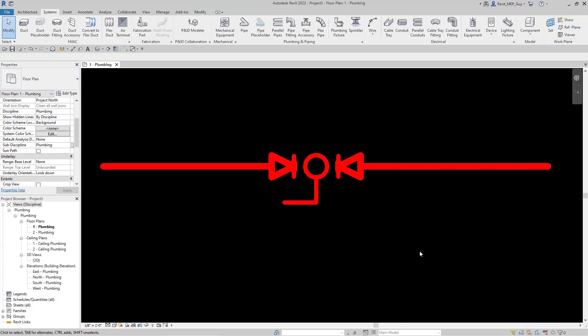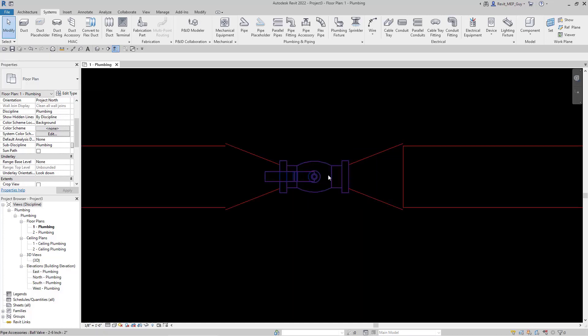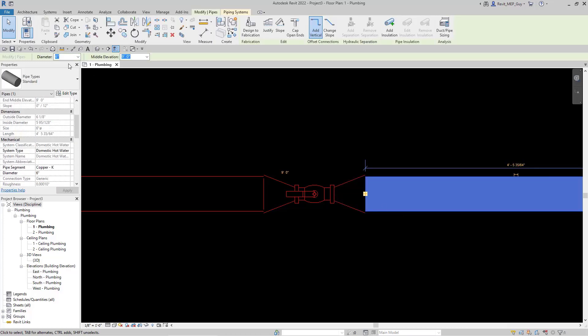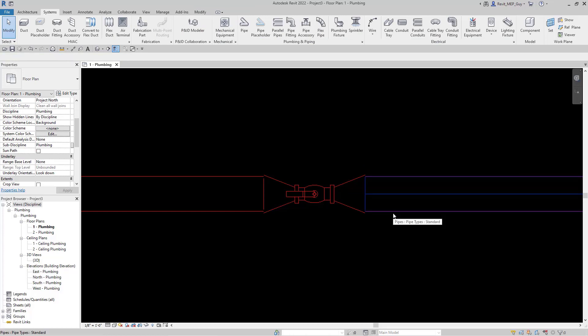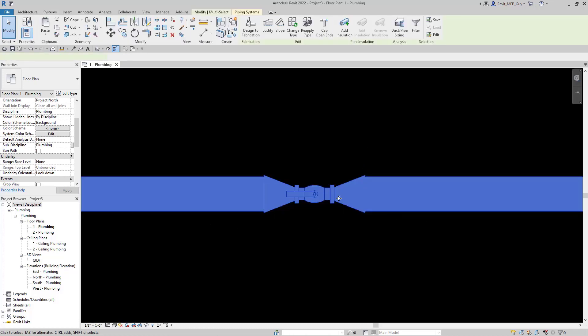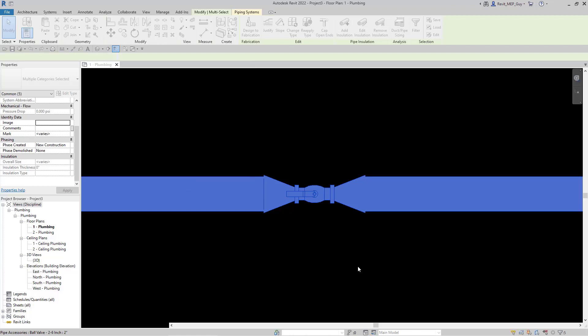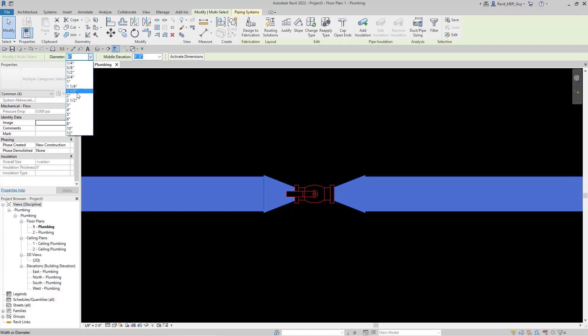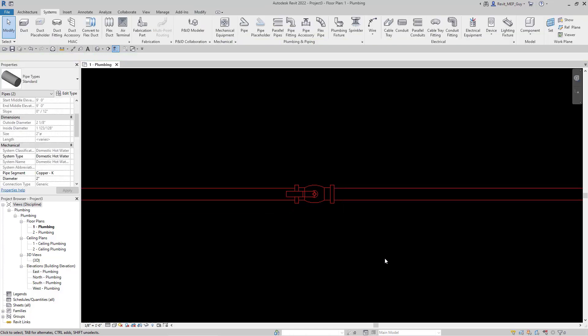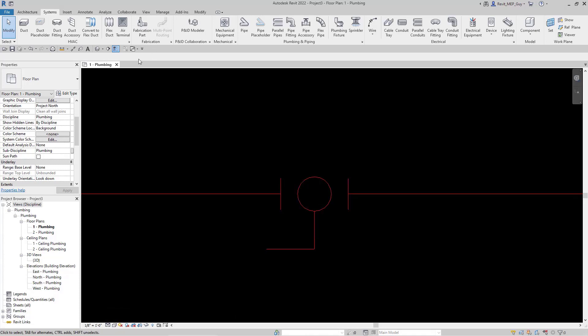We need to change this sizing, so I'm going to go down here and change it to fine level of detail and turn on our thin lines command so we can really see what's going on. Our piece of pipe right now is six inches, so we want to reduce that to two inches. I'm going to tab all of this piping network and the ball valve, go to filter, and deselect my pipe accessory because I don't want to change the size of that. Now Revit's allowing me to change the diameter, so I'm going to change it to two inch to match this ball valve size. Everything looks good now.